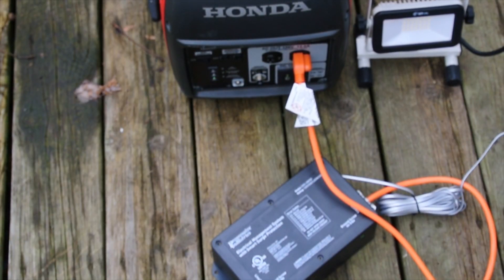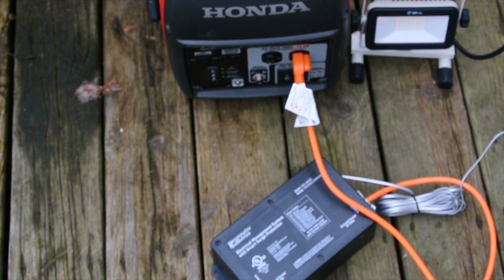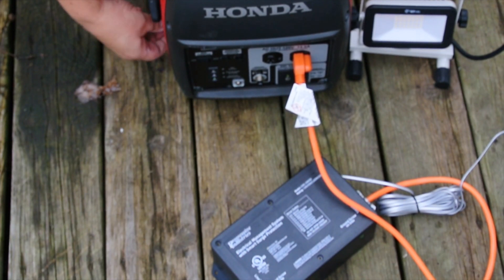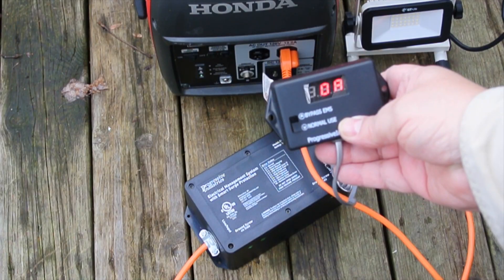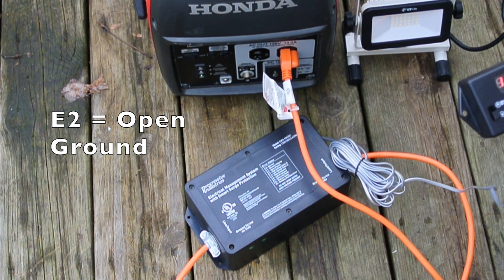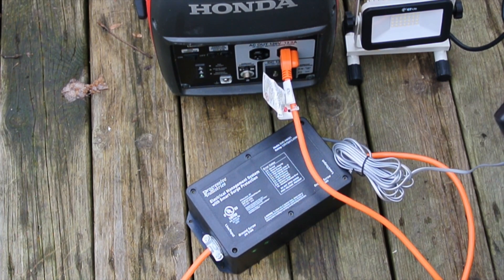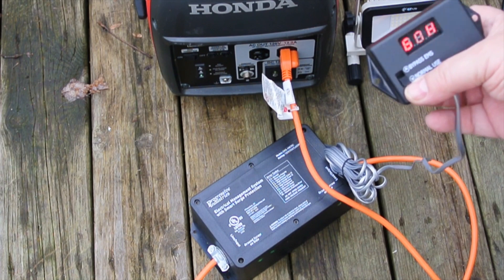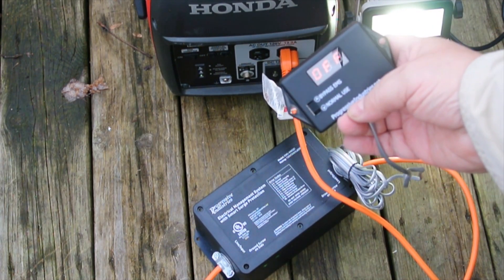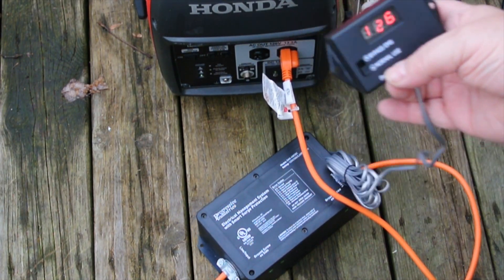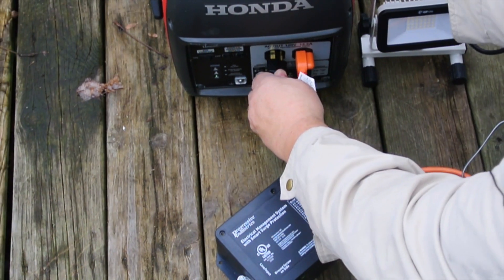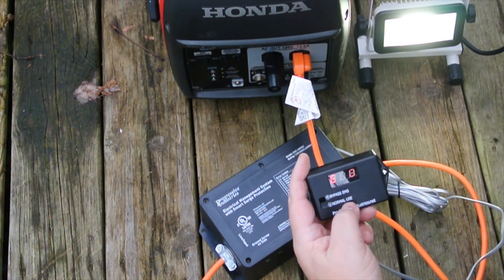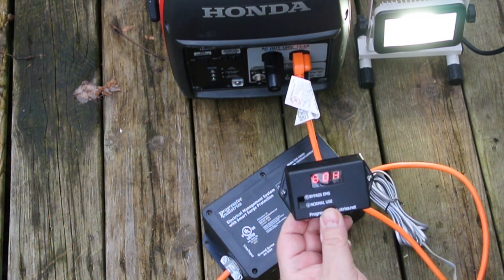So here I have a setup that is similar to what we had inside. I've got the generator connected to the EMS system with an LED fixture on the output, so we can see if it's on or not. And you can see here we have an E2 error. E2 error means open ground. So you see that the LED is not on. But if I flip it into bypass, now the LED is on, so it's working. However, we no longer have any protection. But then if we take our grounding plug, plug that in. And resetting it, we have an E0, and now it's working with the shorting plug.